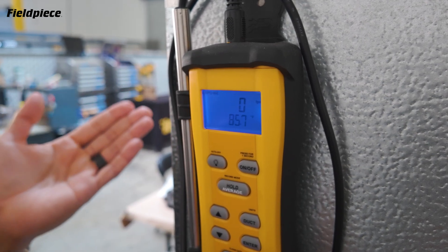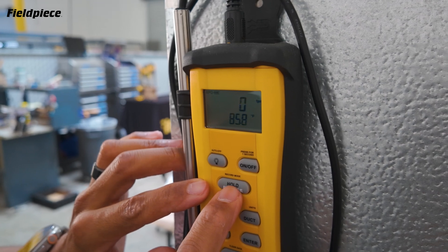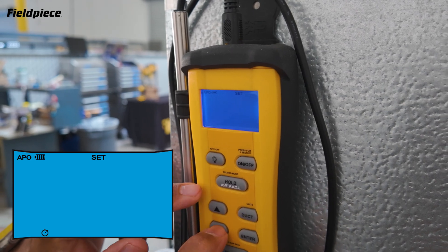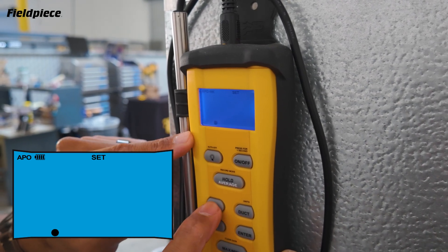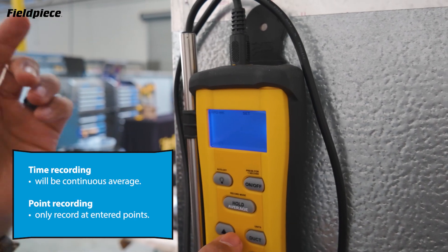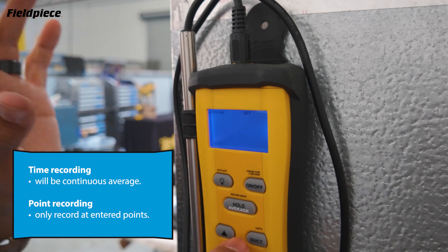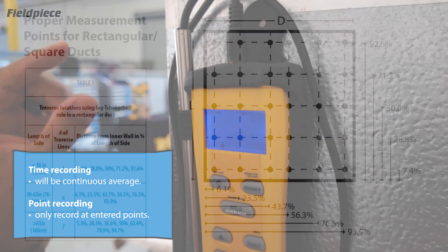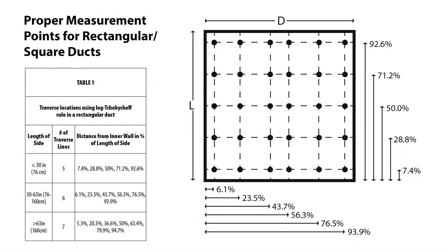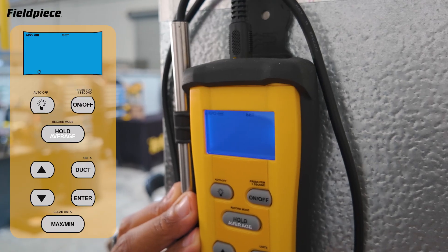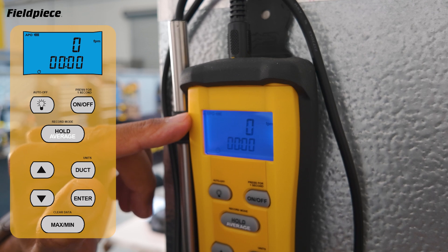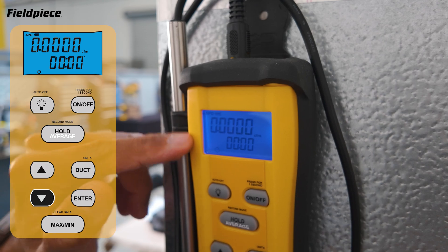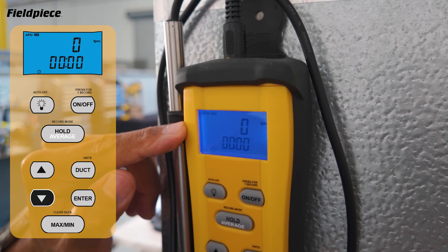Now our duct size is set and we're ready to start a timed average of the CFM. We press the hold average button for a second to get into record mode. From here we can choose between a timed recording or a point recording by pressing the arrow button. A timed recording takes the average of the airspeed for the total time the sensor was in the duct. A point recording takes the average of several individual points taken inside the duct. For this test we're going to use a timed measurement. Press enter and we see feet per minute on top and the timer ready to start.